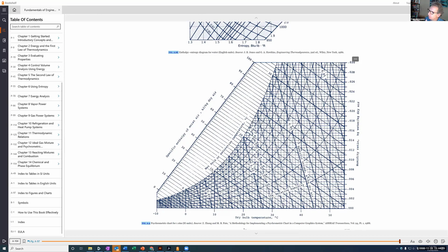But more importantly, as this process is taking place in a transient way, the steel temperature keeps going up and up, and the air temperature keeps going down and down, right? Because as we're moving from point 1 to the left, the dry bulb temperature, which is the temperature that a thermometer in the air would tell us, keeps going down. By the time we're here, we're at about 10 degrees Celsius. The steel started at minus 10 Celsius. If the steel is not at plus 10 Celsius at that point, we're not in equilibrium, right? The steel is still too cold.